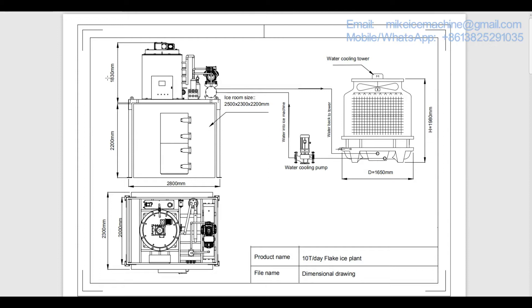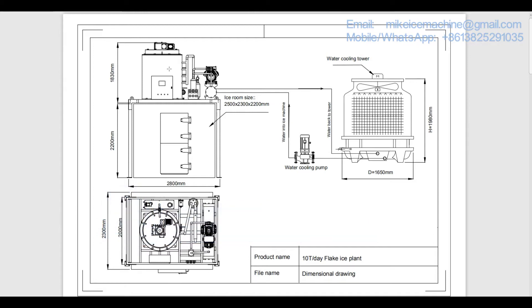This is the drawing to show my standard 10 ton per day flake ice plant. This is the 10 ton per day flake ice machine. This machine can make 10 tons of ice flakes within every 24 hours. That capacity of 10 ton per day is based on working with 30 degree Celsius ambient temperature and 20 degree Celsius water inlet temperature.